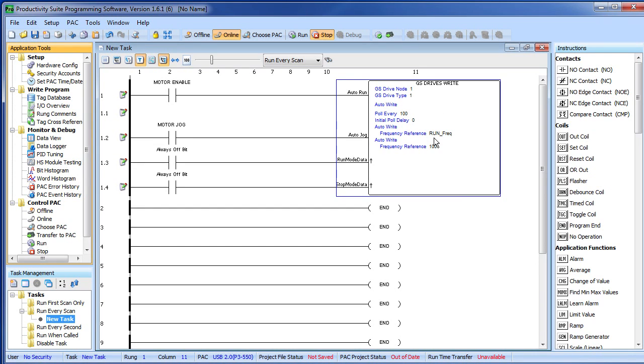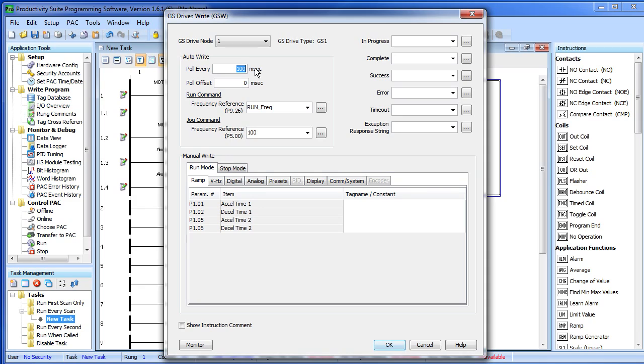Next, you need to make sure that your GS drive write or read are set up with a polling time that is faster than the time out you just set in parameter 905. It's this polling that the drive is looking for. If it doesn't see this within that time out that you set in parameter 905, then it will react accordingly.